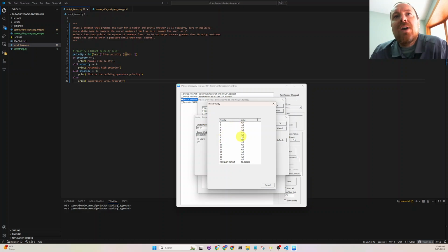So if you had a really complicated building where they designed, let's say, an elaborate smoke sequencing, some kind of really important fan control, where if the fire alarm goes off they need smoke purging, something to happen, they might even say to put that on a higher priority than what the building operator can write. So they would put the logic up here, and then anything below, the building operator can write over it.